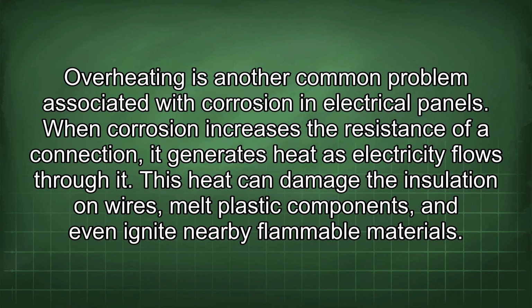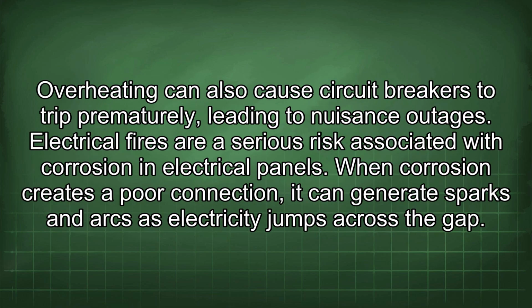Overheating is another common problem associated with corrosion in electrical panels. When corrosion increases the resistance of a connection, it generates heat as electricity flows through it. This heat can damage the insulation on wires, melt plastic components, and even ignite nearby flammable materials. Overheating can also cause circuit breakers to trip prematurely, leading to nuisance outages.